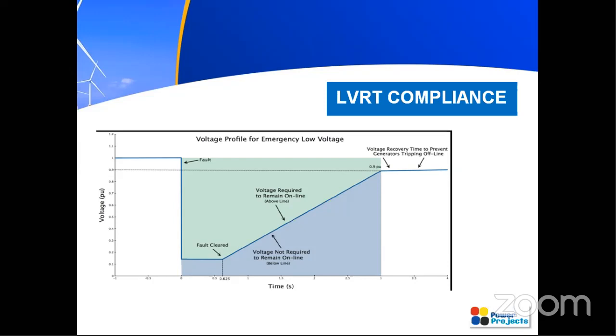So I will tell you the exact lines from the grid code requirements. That is, the generating station should be connected to the grid, and it should remain connected to the grid when the voltage at the interconnecting point on any or all the phases dips, as depicted by the thick lines. Actually, here a thick line is depicted. It shows the variation of voltage from 0.9 per unit to nearly 0.15 per unit. You can see here, it is 0.15 per unit.